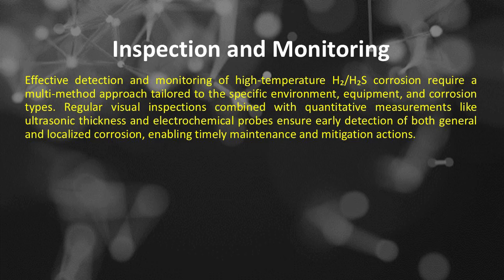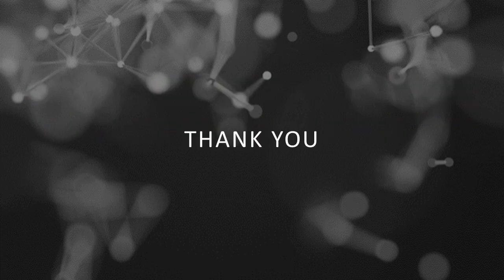Effective detection and monitoring of high-temperature hydrogen (H₂) and hydrogen sulfide (H₂S) corrosion require a multi-method approach tailored to the specific environment, equipment, and corrosion types. Regular visual inspections combined with quantitative measurements like ultrasonic thickness and electrochemical probes ensure early detection of both general and localized corrosion, enabling timely maintenance and mitigation actions.